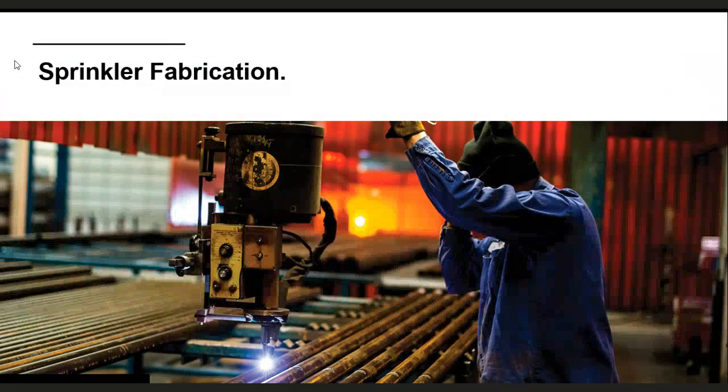So there's lots of things that we do already and have been doing for many, many years, such as sprinkler fabrication. So pipe work can be pre-cut to length, it can be pre-drilled, so there's lots of fabrication works that we can do in advance, and again that's quite common to see, mainly because cutting, grooving, putting pipe threads on, all of that, it requires quite specialist equipment, quite heavy equipment, and definitely with some processes, if you were doing them on site, it would require various permits, etc., which again all just adds time and hassle and cost to the project.